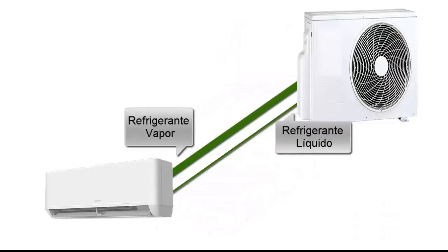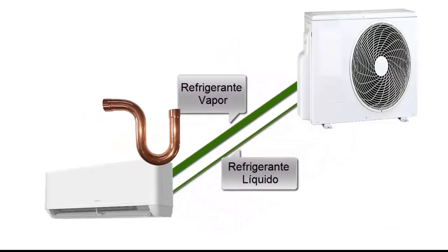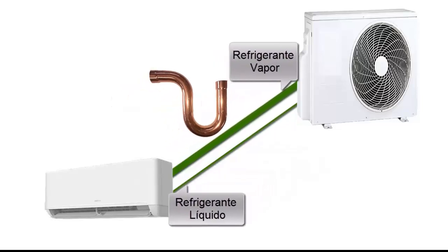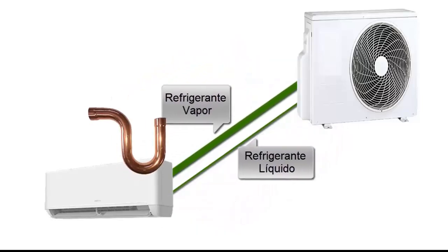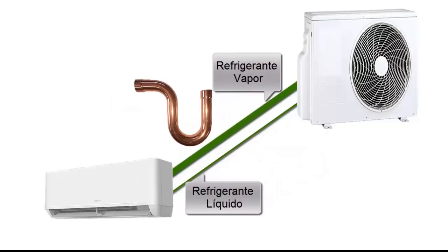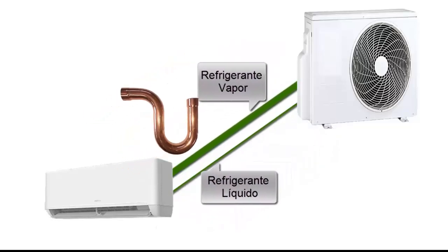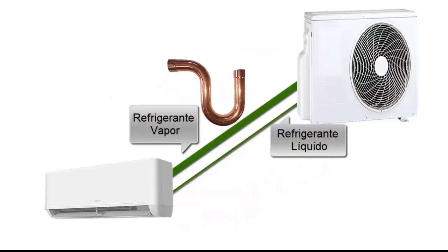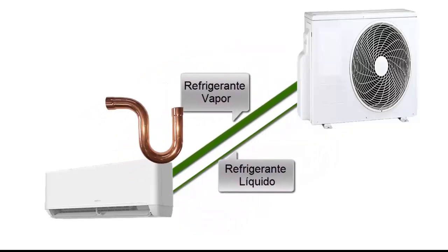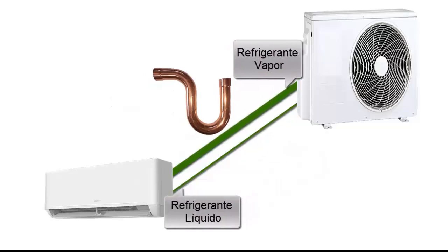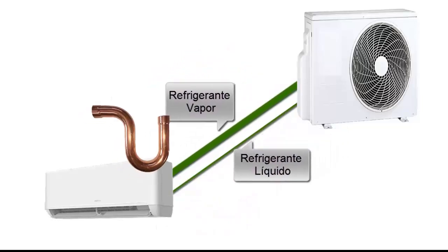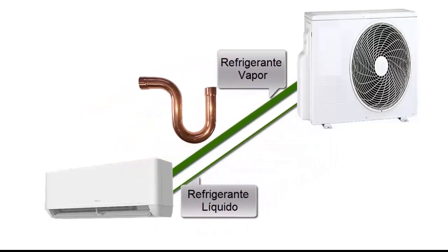Option 3. Indoor unit below the outdoor unit. A. To ensure the return of oil from the indoor unit to the outdoor unit in systems with a large separation, we must create oil traps in the thicker pipe. These traps must be carefully made, as unnecessary pressure drops in the thick pipe directly increase electrical consumption.